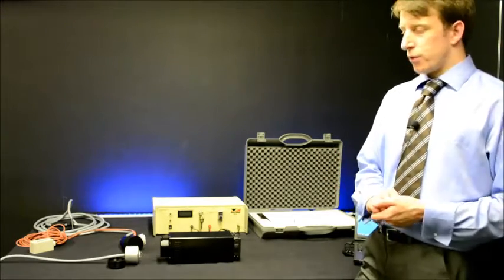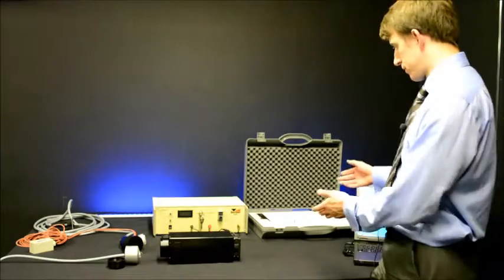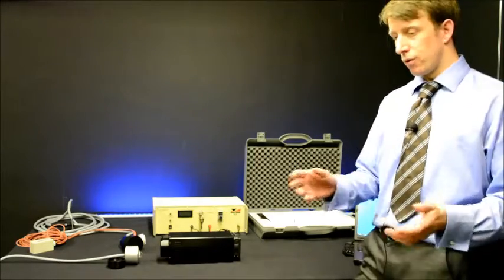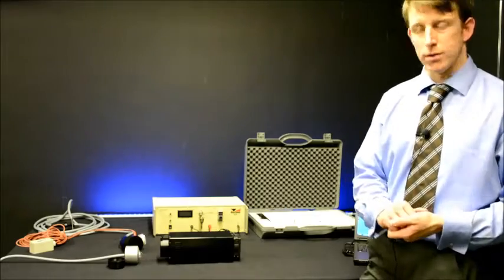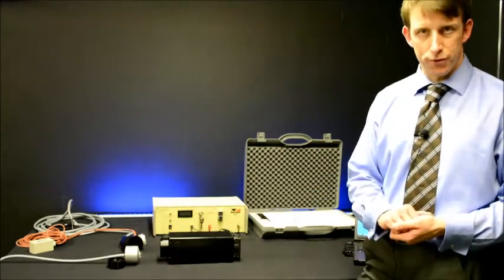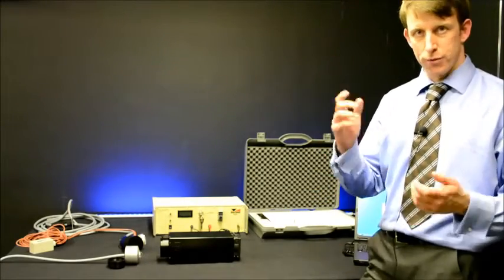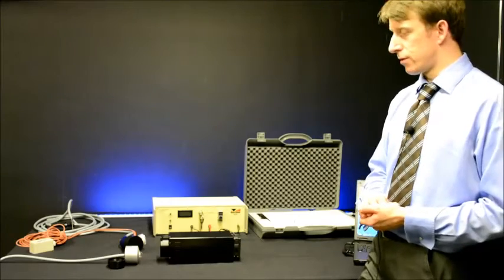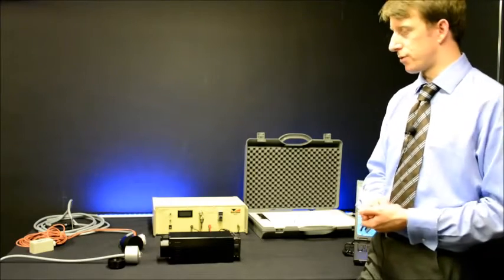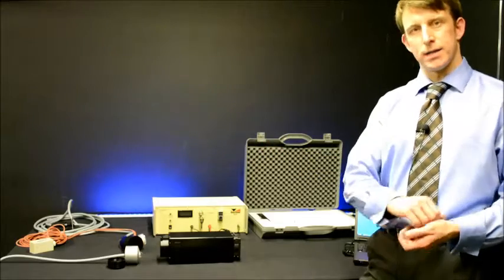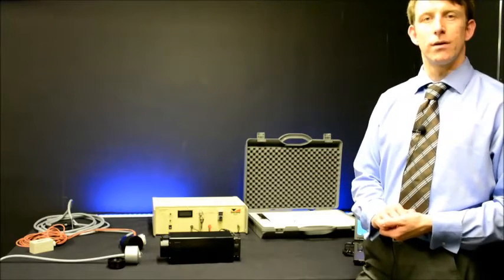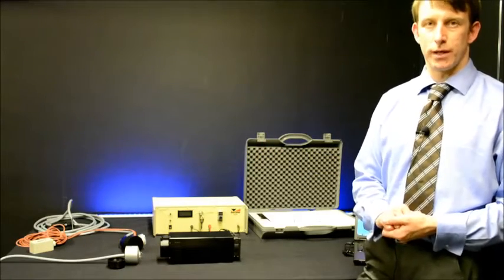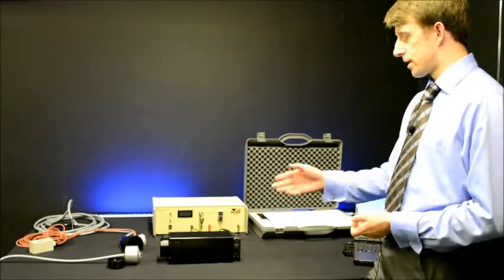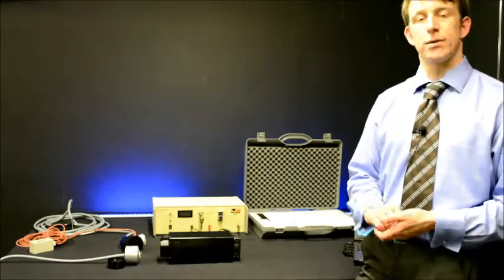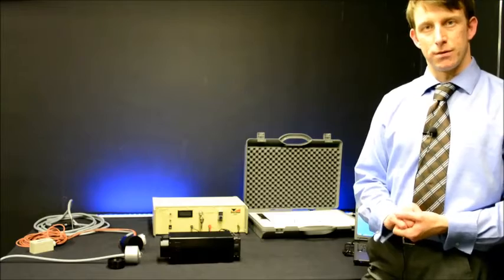Ideally, one would have the darkroom for use of the kilowatt lamps close to the enviroboxes, so one can simply remove the diffuser from the outdoors area where the input optics are kept for measurement of solar irradiance and take it directly to the darkroom for calibration with the kilowatt lamps. The CL6 can be brought outside, for example, for calibration directly in situ.